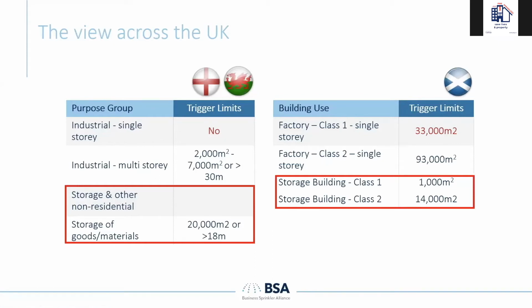Go north of the border to Scotland, and they take an approach based on building use: storage building class 1 or storage building class 2. Storage class 1 is for flammable liquids type special hazard storage, at 1,000 square meters as a compartment size, so you'd need a wall or enclosure around that. For more general warehousing, it's 14,000 square meters.